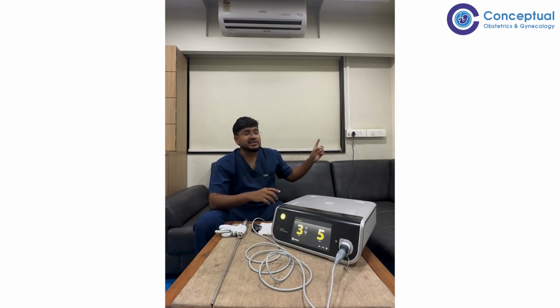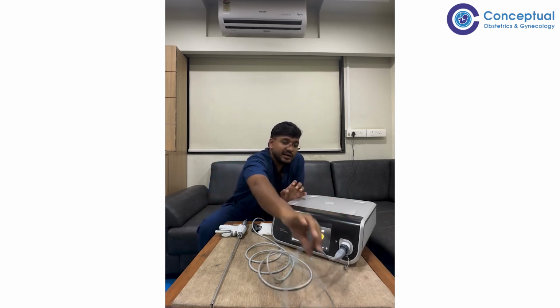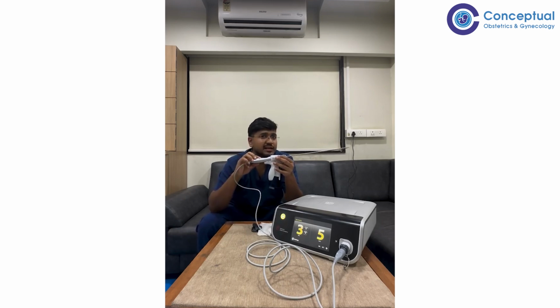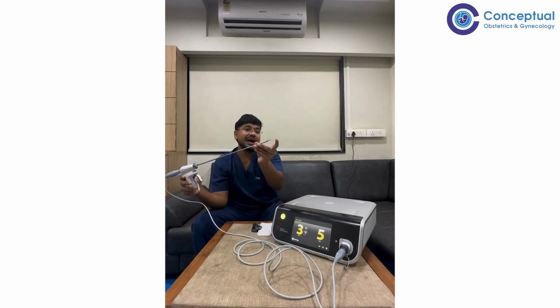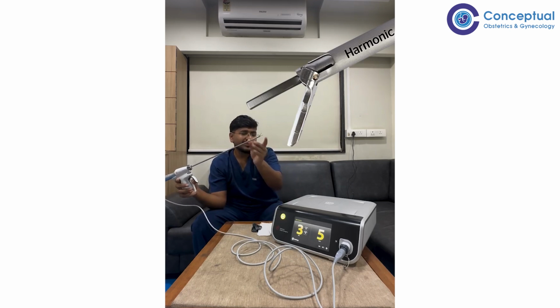So how is this machine actually converting into the action of coagulation and cutting? Let us look into the mechanism of action. From the electric source, this electric generator produces electric current. The electric current now travels through the wire and it enters the transducer. Inside the transducer, there are piezoelectric crystals under high pressure. These piezoelectric crystals expand and contract, which causes displacement of the active electrode, which is here. This causes inside and outside movement of the jaw.